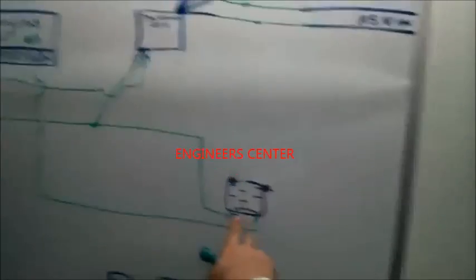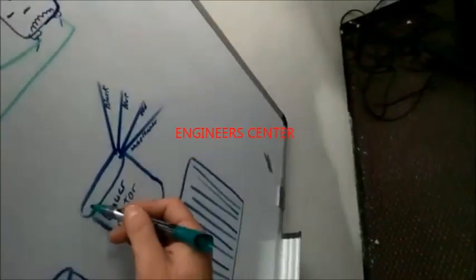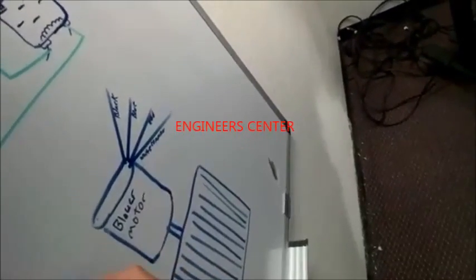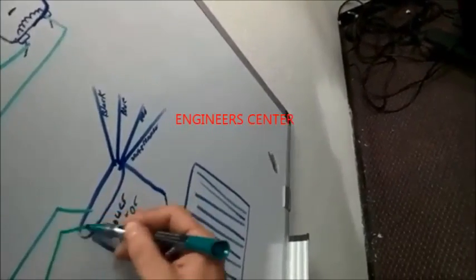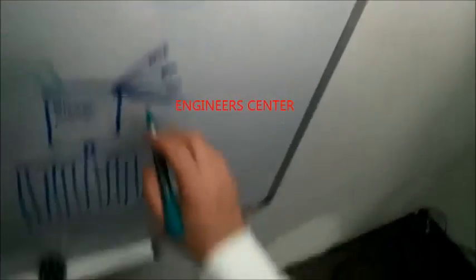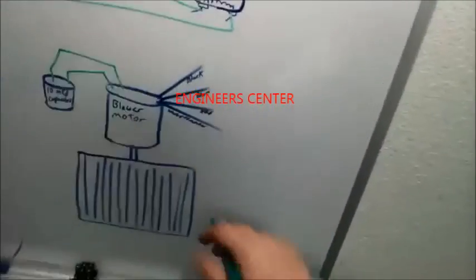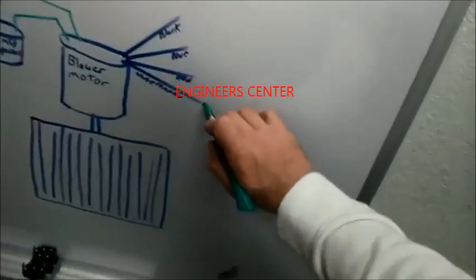So now the only thing we're lacking is a blower motor. We gotta have airflow in order for the stuff to work. We already brought this coil on with our low volt, so let's just simply wire our blower motor. We know it's gonna need a capacitor into the two brown wires of the blower motor. Now we got our speeds here. It's a 3-speed motor. We got white, usually common. We're going to give that straight to one side.